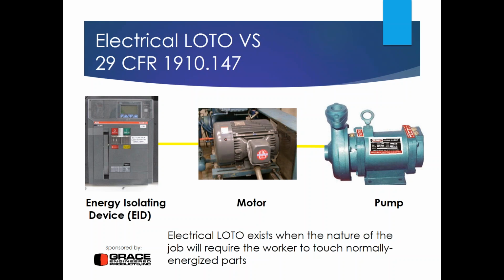If that is not the case, as in the situation where we were changing out the pump, which in my example is driven by a mechanical shaft and has no electrical parts in it, then straight up 1910.147 would be applicable. On the other hand, if we were going to change that motor out, you see the cover there on the T leads on the motor. If we were to remove that cover to do the voltage checks we would need to do, of course, that would require electrical lockout. So that's one thing to know: the difference between electrical and mechanical.